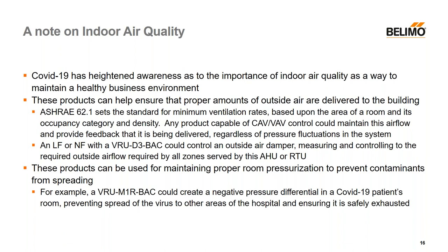Occupancy category matters — a gym, for example, requires a lot more fresh air per person because people are active, producing more CO2 and sweating, so you need more fresh air compared to someone sitting in an office. Occupancy density is also an important consideration — how many people will be in that room. A good example is a college classroom versus a lecture hall: students in both are doing the same thing and sitting down, but a classroom has fewer people per area than a lecture hall where seats are packed together. You're going to need more airflow when you have more people per area.